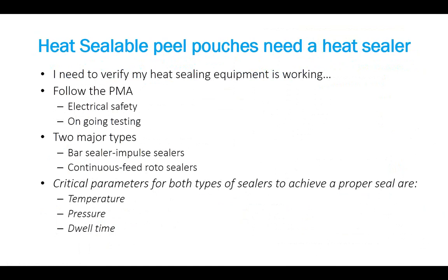Each pouch has its own specific temperature range, depending on the laminate, whether it's Tyvek or paper, that it must reach to melt. There must be a certain amount of pressure or force applied at that temperature, and a dwell time, how long that temperature and pressure are applied to create the seal. That's what's important to create a good, heat-sealable seal.